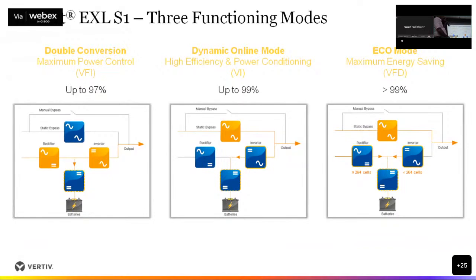And the disadvantage we talked about: your load disturbances are exposed to the utility, whereas here it is not exposed to the utility, because the inverter acts as a hybrid inverter. It charges the battery. Also, it acts as an active filter, where it compensates the load harmonics and power factor continuously and keeps your upstream always healthy, as well as improves the efficiency to 99%.